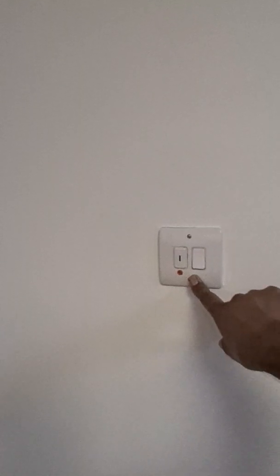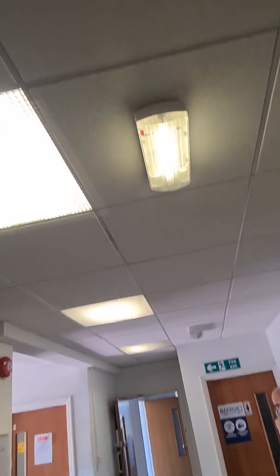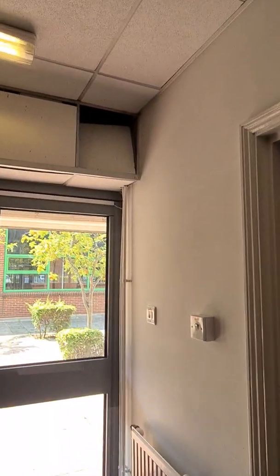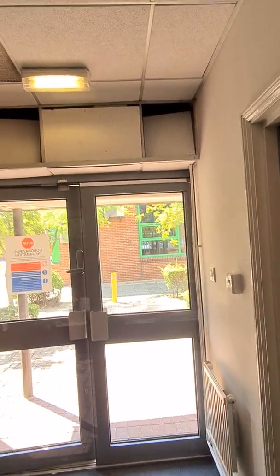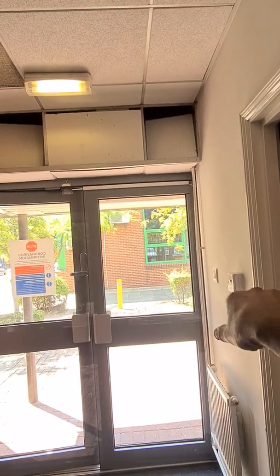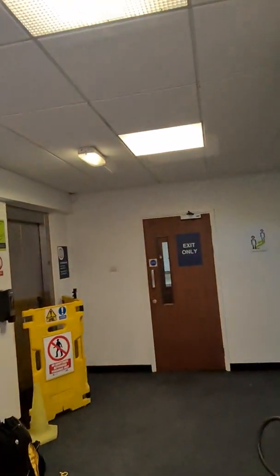we've got the next one here next to the lift lobby, and that affects all the lights here in the lift lobby area as well. So you've got an emergency light here and this one here, which has failed. Now, the light switch here, I forgot to say, also affects the ladies' toilet. There's an oblong emergency light in there as well. So you've got 3 lights that work off of this one emergency light test switch, which we've labelled as FK1. And the one there is FK2.